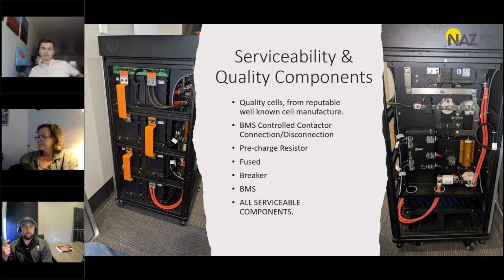When you start the battery up, it'll go through a pre-charge resistor. There's a big pre-charge resistor on the right-hand side that allows you to charge the caps in the inverter whenever it's starting the connection up, which is a very important takeaway. If you have a FET-based BMS without a pre-charge resistor, you can subject that BMS to maybe 4, 5, or even 10 times what it's capable of handling. A pre-charge resistor keeps that current flow minimal so it can charge the caps, then close the contacts and provide power to the system.